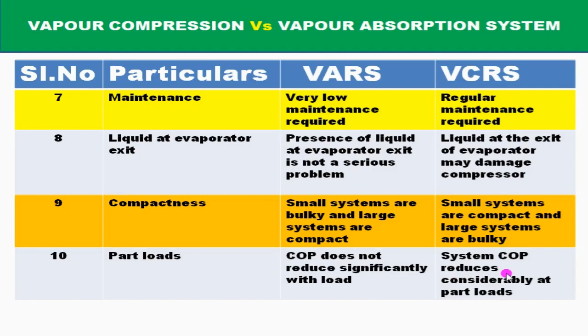Part load. COP does not reduce significantly with part load in case of vapor absorption refrigeration system. In vapor compression system, COP reduces considerably at part loads. Charging of refrigerant, that is filling of refrigerant, in vapor absorption refrigeration system is difficult and in vapor compression system is simple.